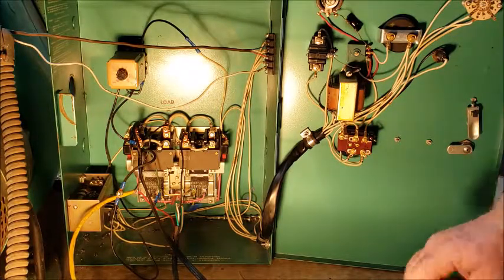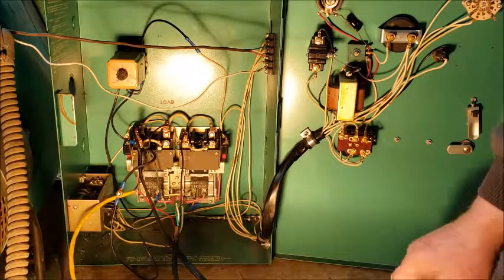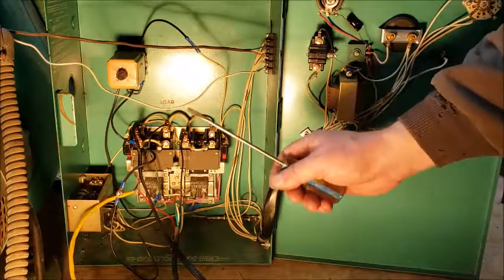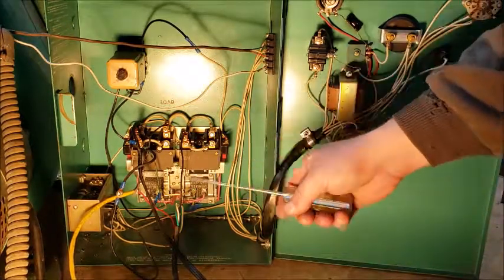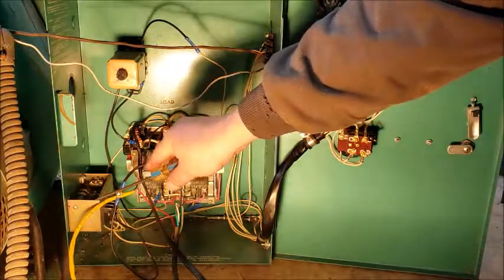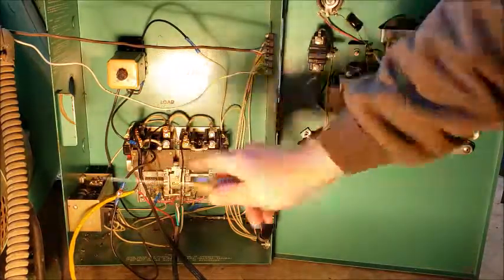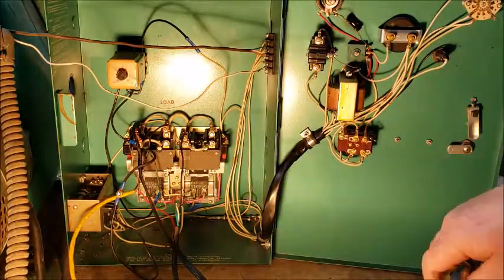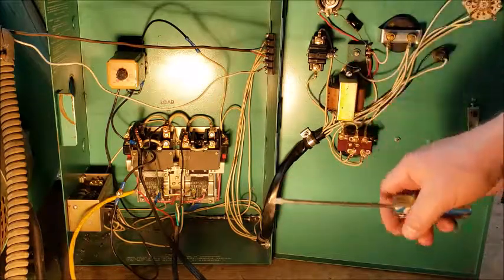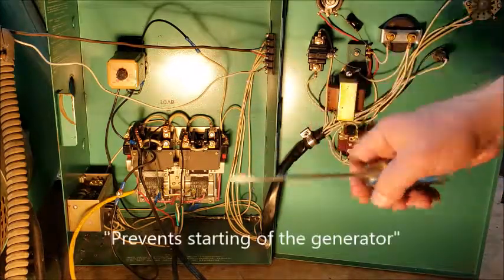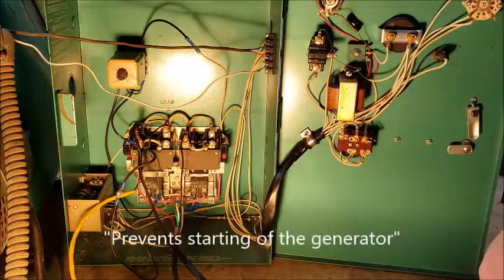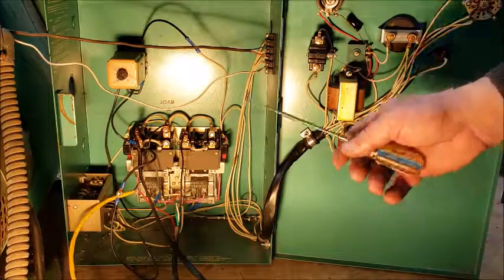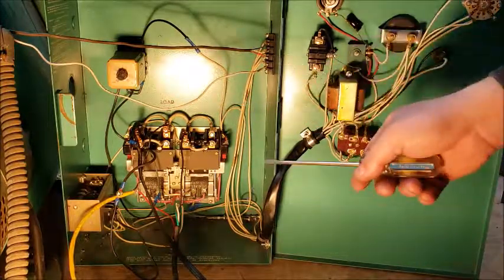Once you have 115 volts from either the generator or line voltage, this start disconnect relay energizes and opens the circuit to prevent starting of the generator. So obviously when you have 115 volts from either the generator or line voltage you don't want the generator starting, so this keeps that from happening.